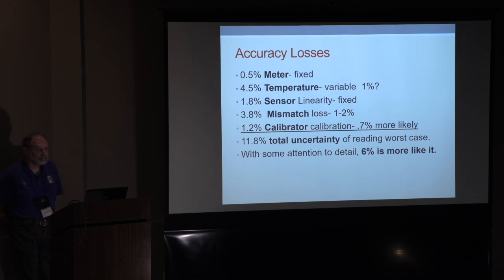All the companies that design those do the same basic thing. They design an oscillator that's fairly indifferent to frequency. It's just an LC network. But they take special pains for output stability and level. And I'm surprised that I can take a 436 that's 20 some years old and put it on the power meter, and it's still within spec. So the uncertainty calculator comes out with 11.8% total uncertainty for reading. It's not of 11% full scale. It's of reading. So that makes it a little bit easier. I think you can get it down to 6% if you work on some of those levels of uncertainty.